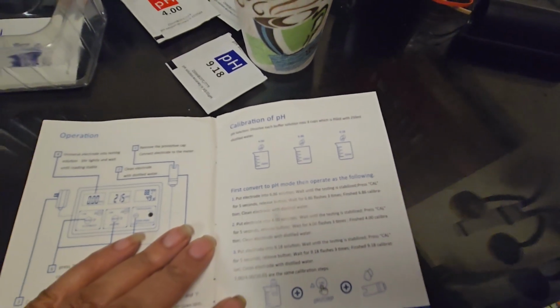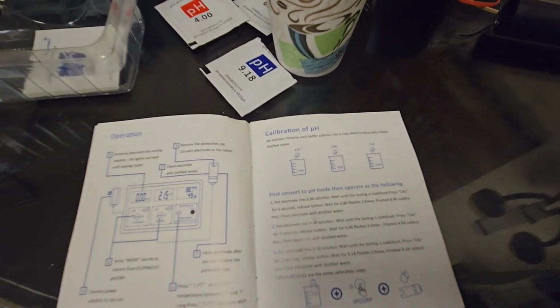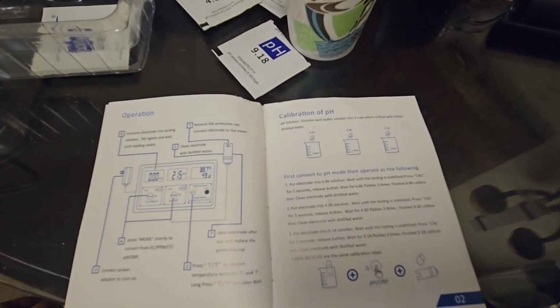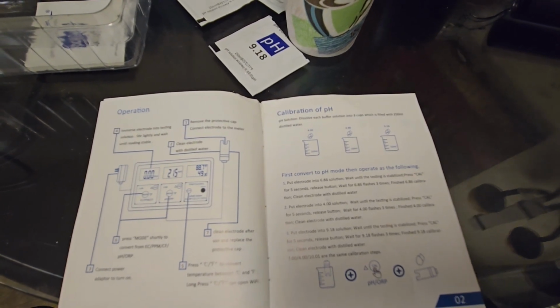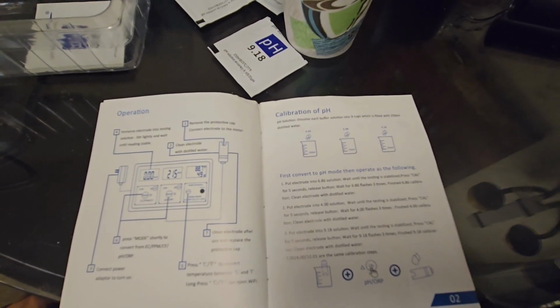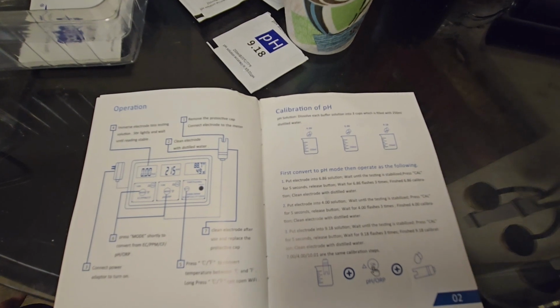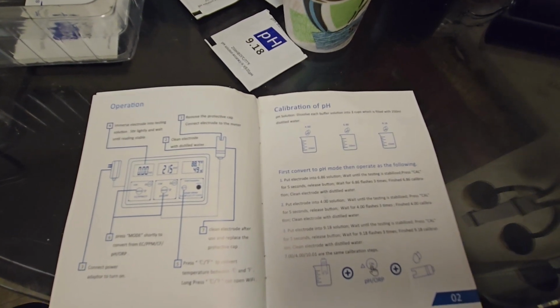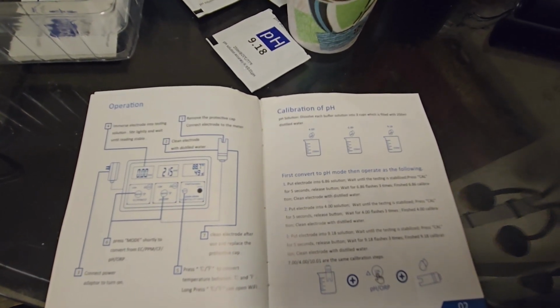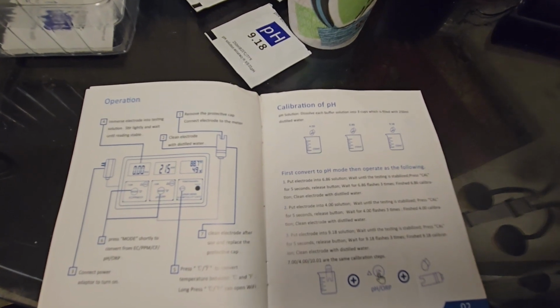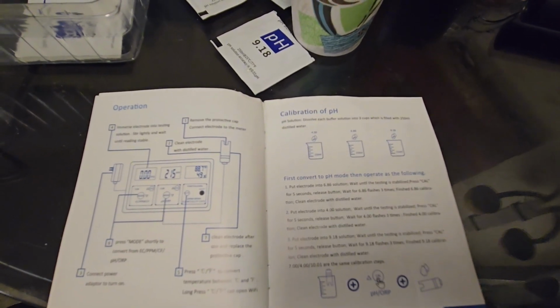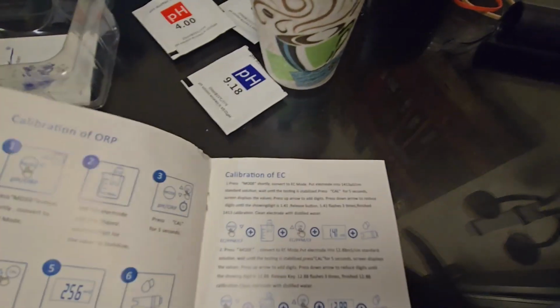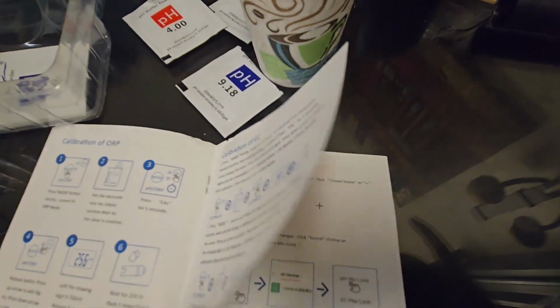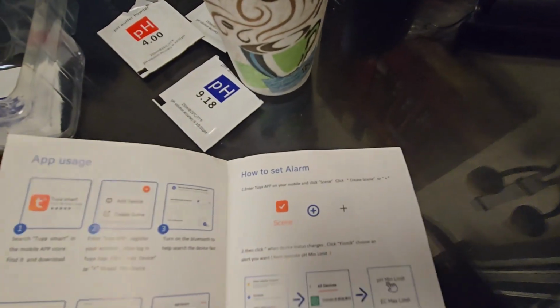The instructions read, put the electrode in the 9.18 solution, wait until the testing is stabilized, press cal for 5 seconds, release the button, wait for 3 flashes, and finish. 9.18 calibration, clean the electrode with distilled water. So it says 7.0, 4.0, and 10.01 are the same calibration steps, but I'm not going to go through that. So I'm going to assume at this point that the pen is calibrated.